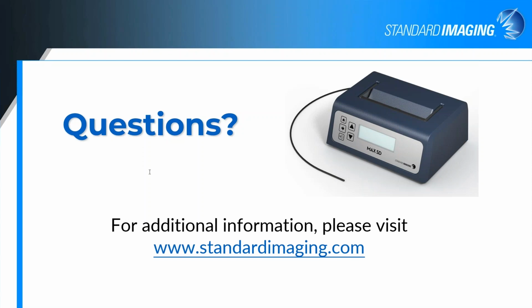And then there's another question: is there an effect of radiation dose response changing over a period of time? Yes, it does decrease slightly over time, and that really has to do with damage to the plastics. We use a PMMA optical fiber, and I'm sure you've seen old clear plastic phantoms. They turn yellow after they've been irradiated quite a bit, and that yellowing does two things to our measurement. It preferentially filters part of the spectrum, which changes the shape of the spectrum slightly, which is why you would need to repeat your Cherenkov light ratio characterization measurements. But it also filters out some of the signal. So your total signal decreases slightly as those plastics age, as they are irradiated more and more.